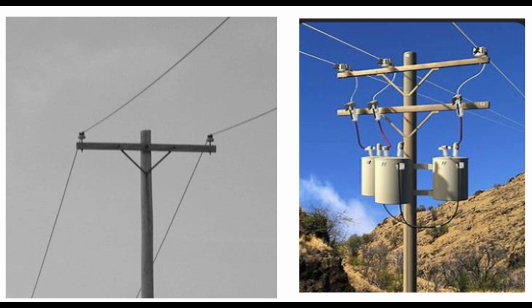This is a comparison of a single-phase 13.8 kV distribution line over a three-phase 13.8 kV distribution network. The limitation of the single-phase line is obvious, as a three-phase transformer cannot be accommodated unless using an open delta connection or using two single-phase 8 kV primary rating transformers connected in open V or delta connection.